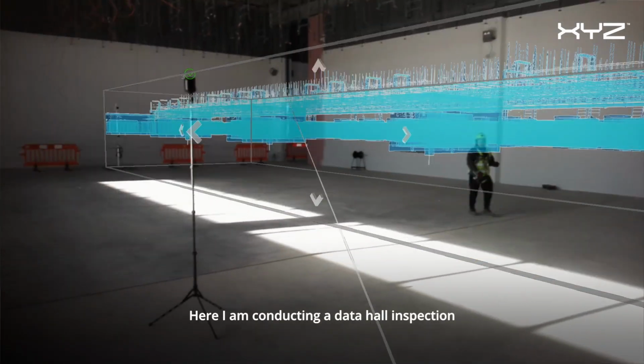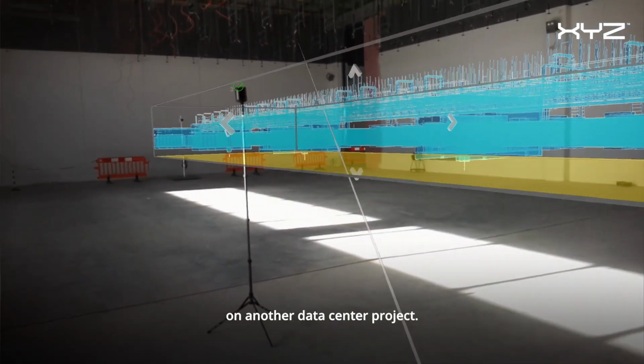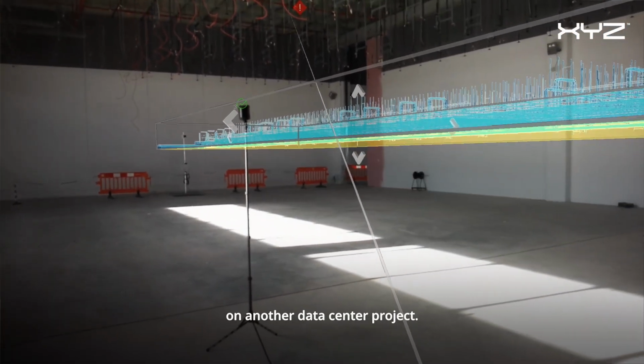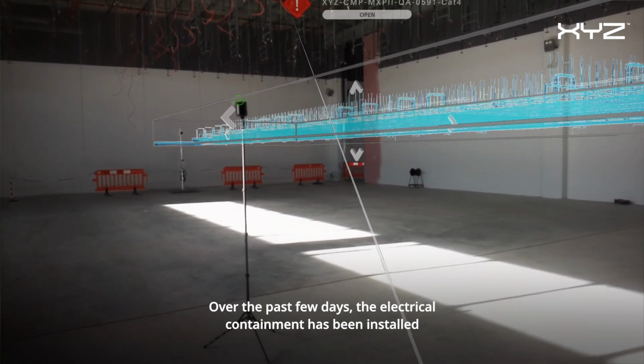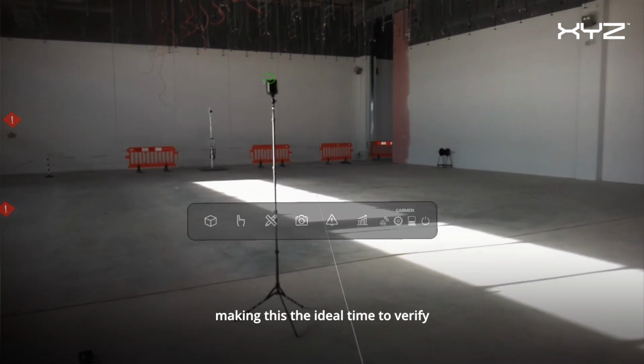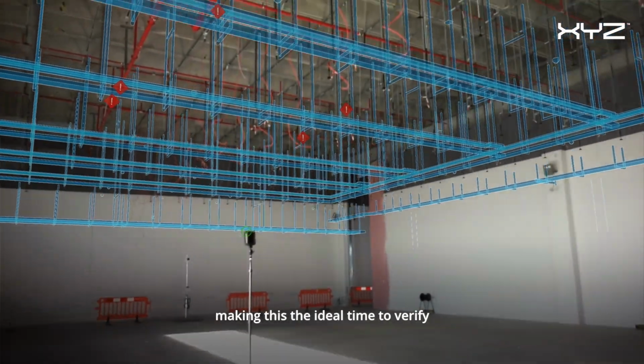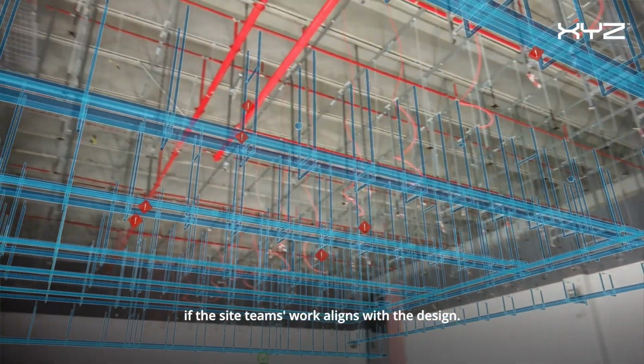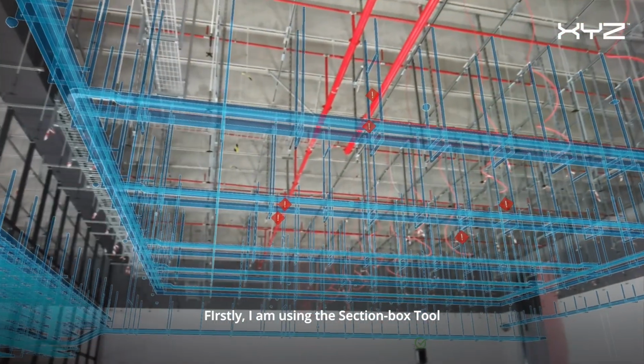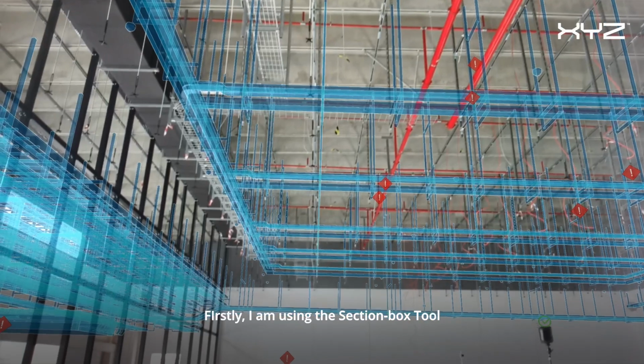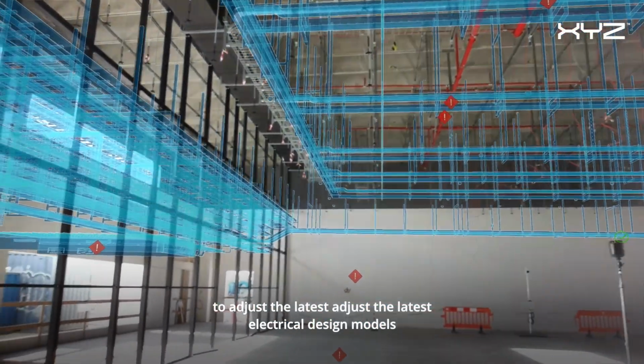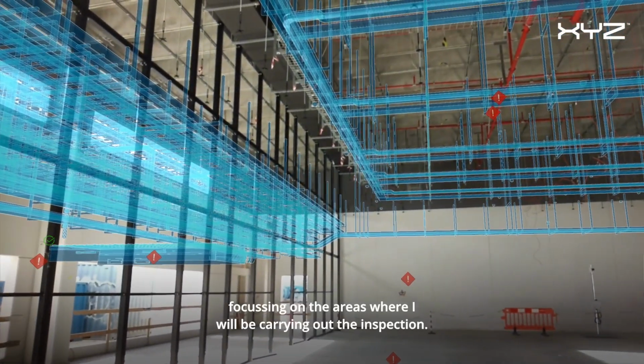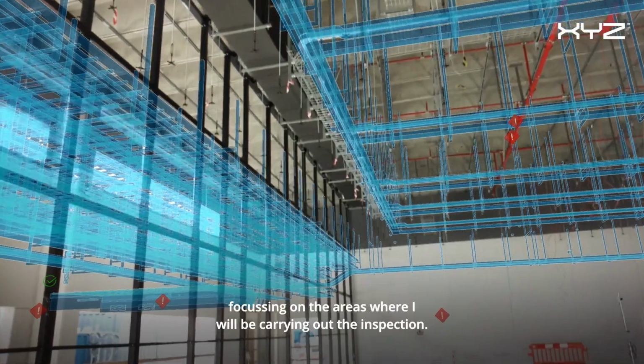Here I am conducting a data hall inspection on another data center project. Over the past few days, the electrical containment has been installed, making this the ideal time to verify if the site team's work aligns with the design. Firstly, I am using the section box tool to adjust the latest electrical design models, focusing on the areas where I will be carrying out the inspection.